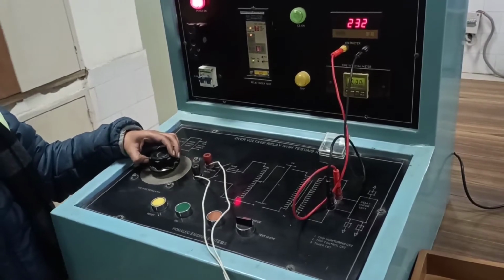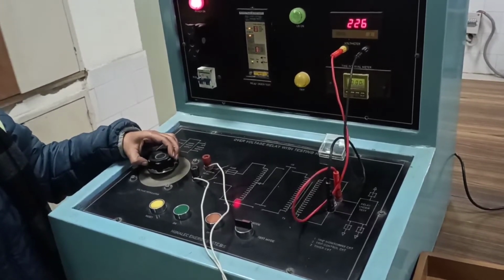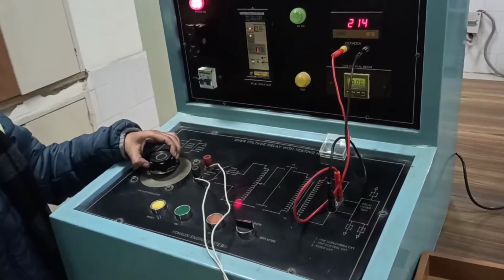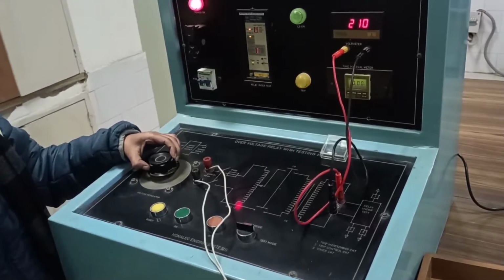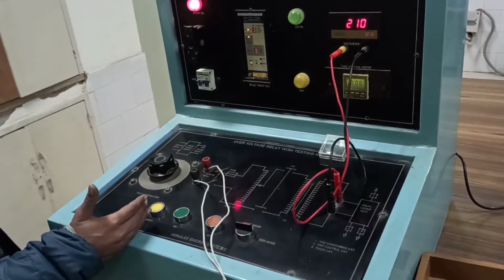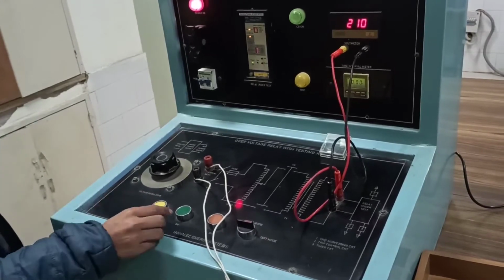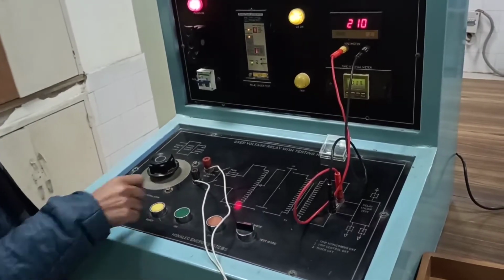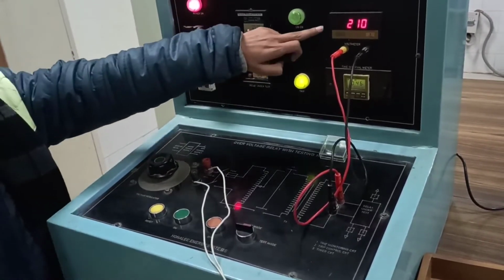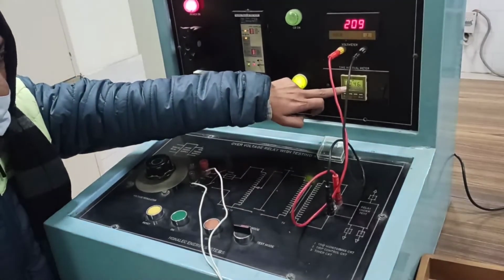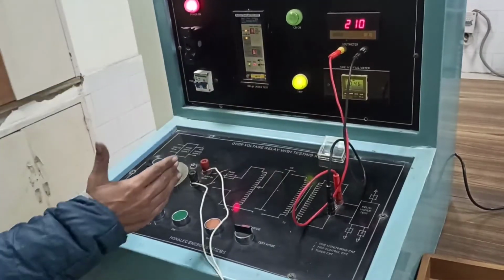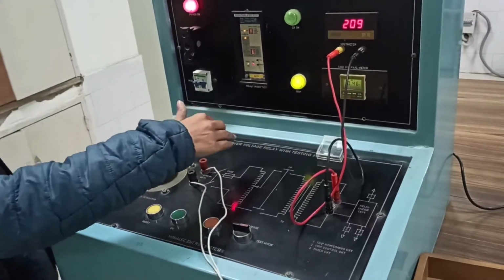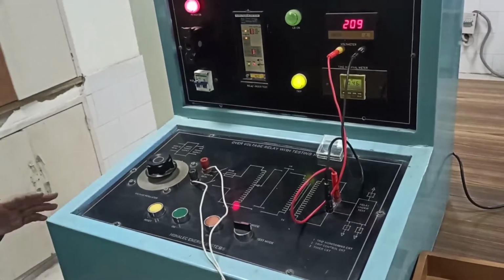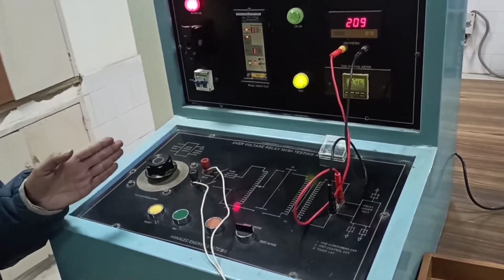Decrease the voltage. Now set to 210 volt. Decrease the voltage at intervals of 20 volt. Now again switch on. Now at 210 volt, the trip time is 0.46 seconds. As we decrease the voltage, the tripping time also increases. This shows the IDMT characteristics.